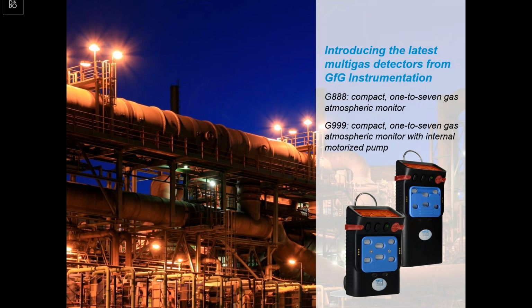But the 888 and the 999, as compact as they are, it's hard to believe these are 1 to 7 channel instruments. We've got room for up to 5 sensors when we use a dual channel IR CO2 IR LEL, or a dual channel COSH sensor for CO and H2S measurement. That gives us an enormous number of 6 and 7 channel combinations. In terms of the compact size of the product and its capabilities, nobody can match us. I look at our honored competitors and their products out there, and I'm really, really happy with the 888 and the 999.